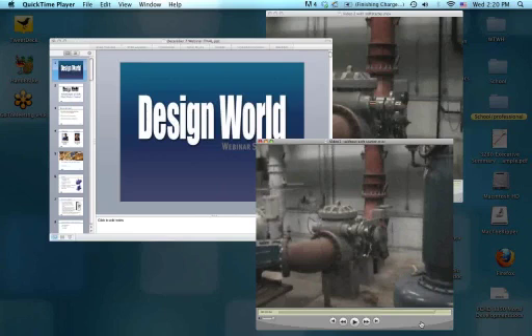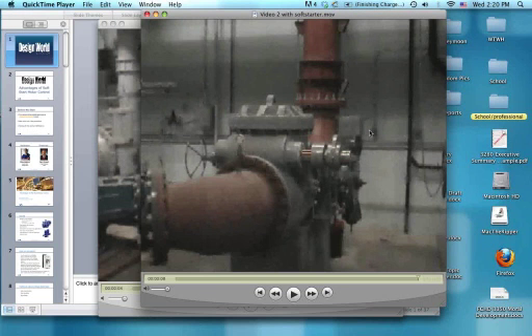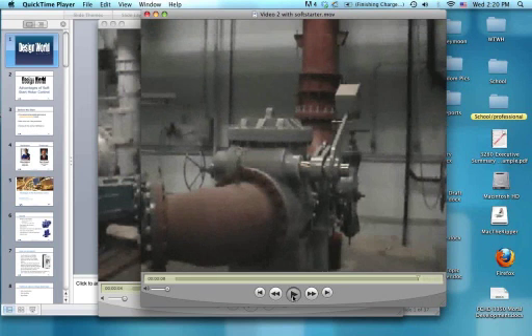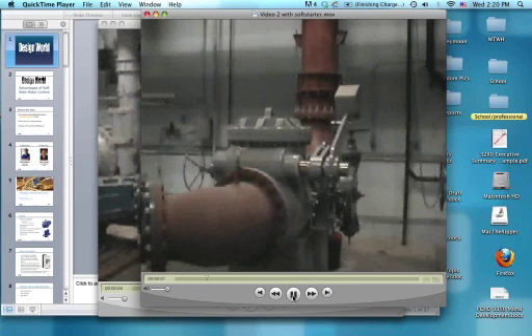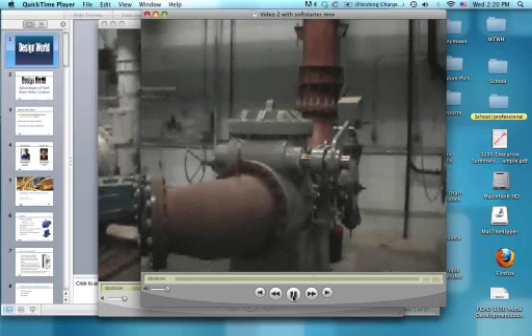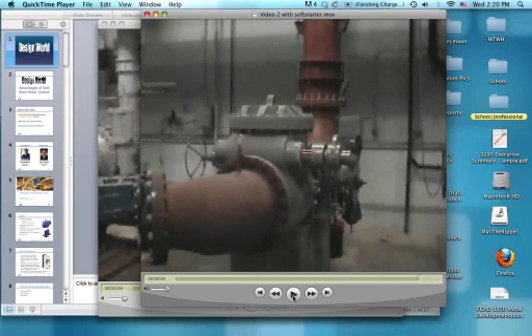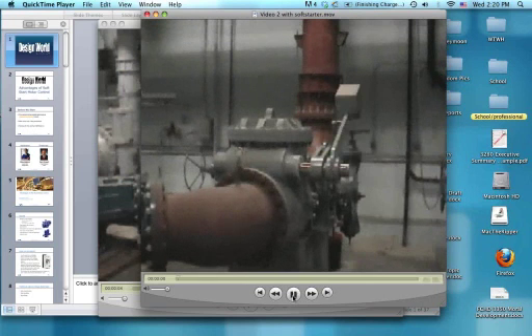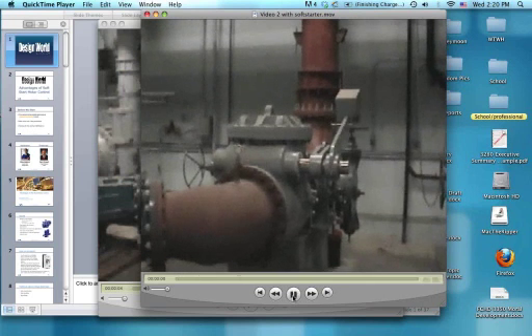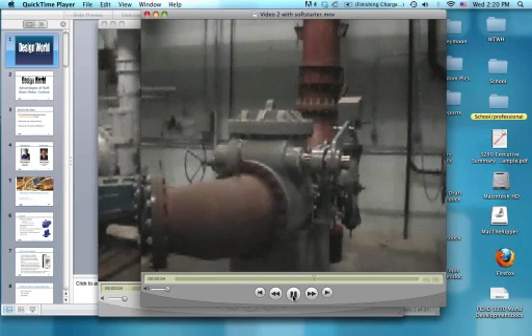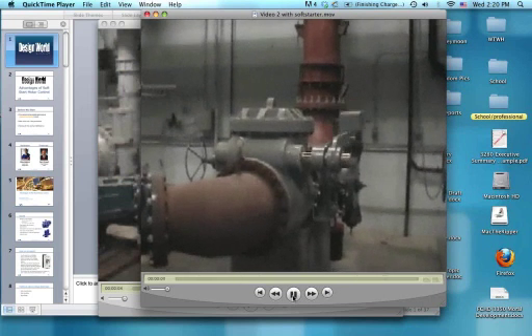Now let's switch to video 2, which shows you the exact configuration, but instead of an across-the-line starter, we are using a soft starter. Now you can see at the end of the pump cycle how the check valve comes to rest. I'm going to run that just one more time. You can see that the check valve movement from the top position to the rest position is much smoother than what we have seen in the previous video.